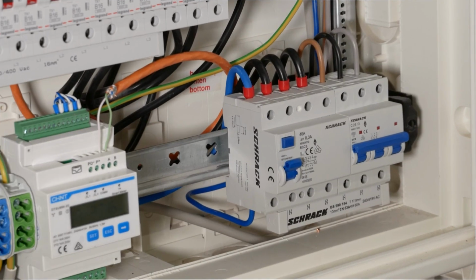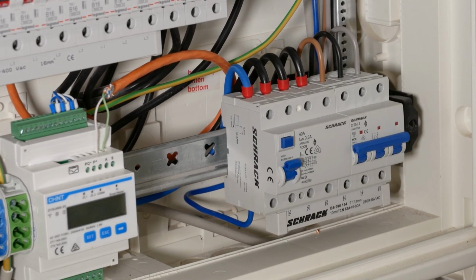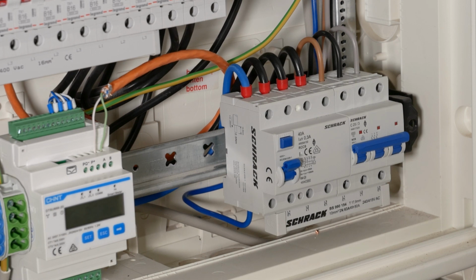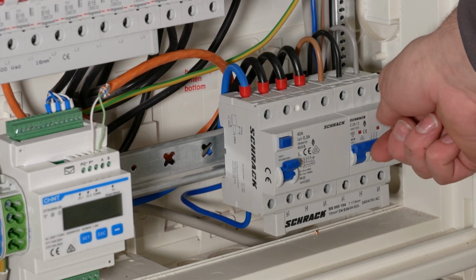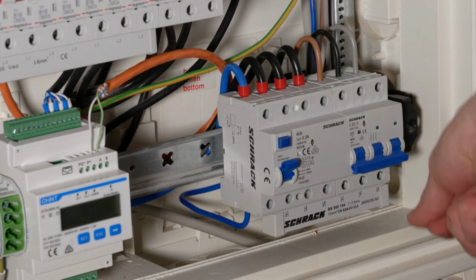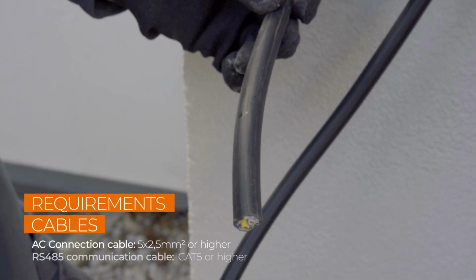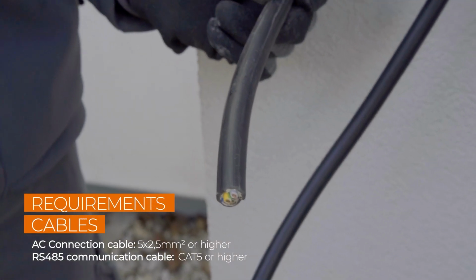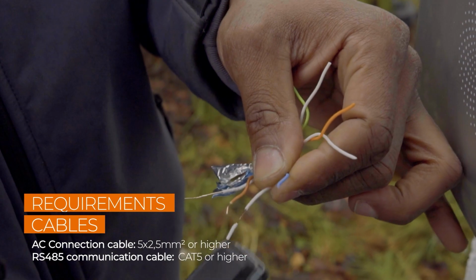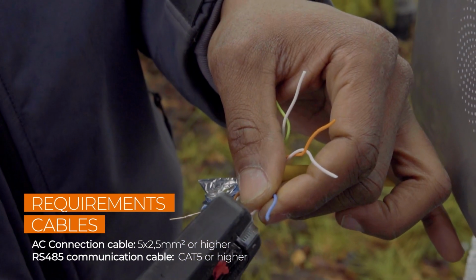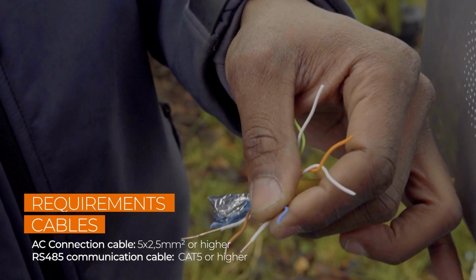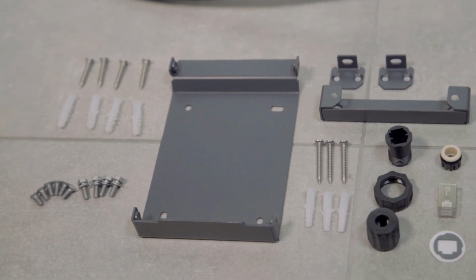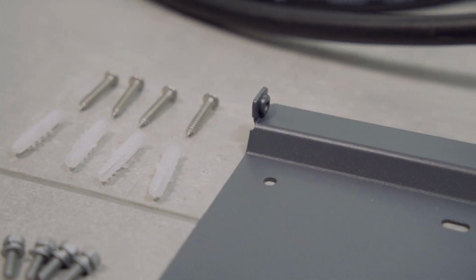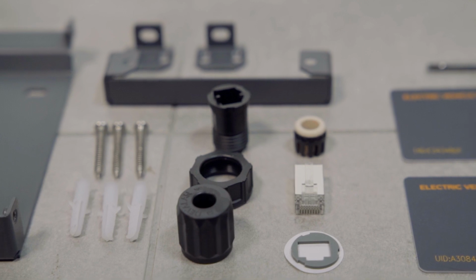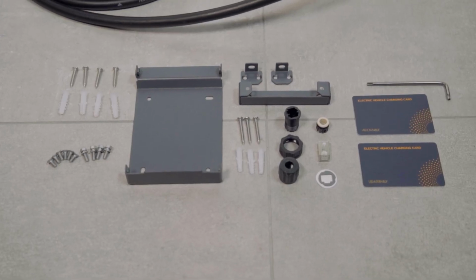Ensure that a 30 mA Type A RCD is installed and that the respective circuit breaker is safely isolated before you begin installing the AC charger. Also, make sure that the AC connection cable and RS485 communication cable have been correctly installed prior to the installation of the charger. All screws, dowels and the mounting plates required for the installation are already included in the delivery. You only need your own installation tools.